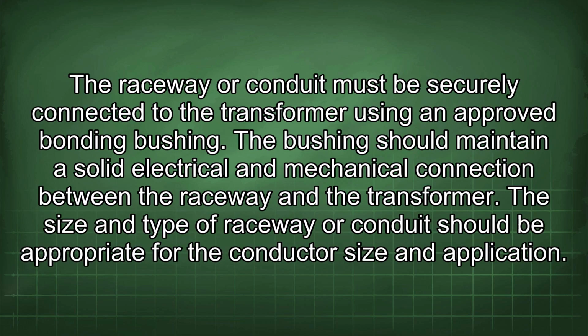The raceway or conduit must be securely connected to the transformer using an approved bonding bushing. The bushing should maintain a solid electrical and mechanical connection between the raceway and the transformer. The size and type of raceway or conduit should be appropriate for the conductor size and application.